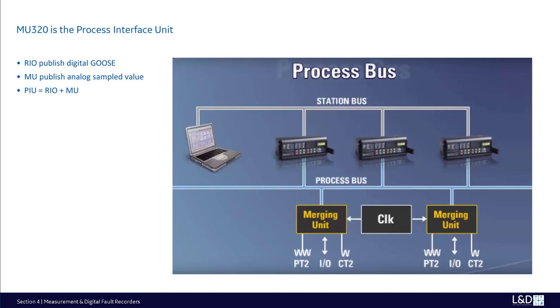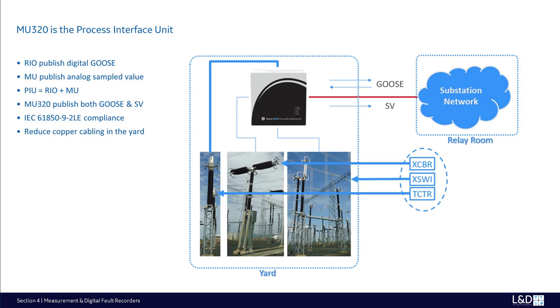Merging units convert AC current and voltage signals in the substation yard to the digital sampled values with a timestamp. A PIU, like Reason MU320, is a bridge between the physical and the digital world, publishing both analog status data in both sampled values and Goose messages and subscribing Goose to control outputs. It is IEC 61850-9-2LE compliant, offers interoperability with other process bus devices, with no reliance on proprietary technique. It aims to reduce copper cabling and trench dimensions in the substation yard thanks to its fiber optical data transmission.